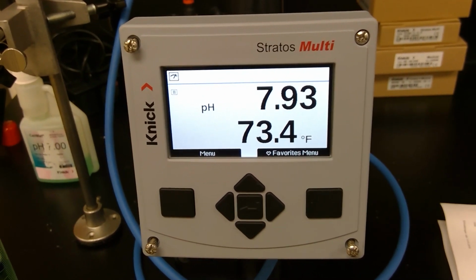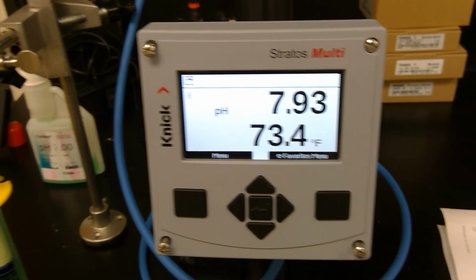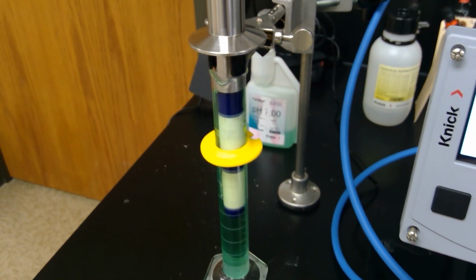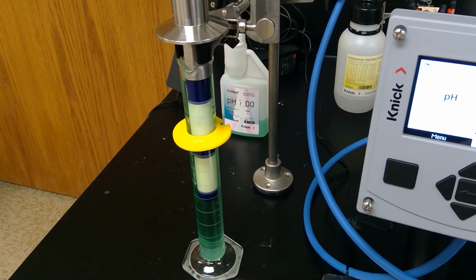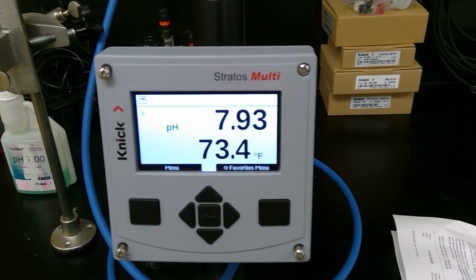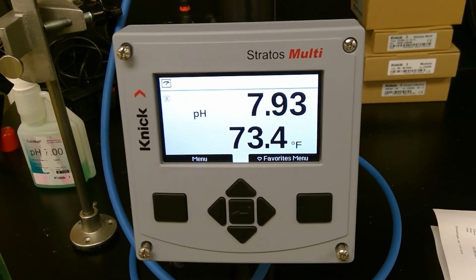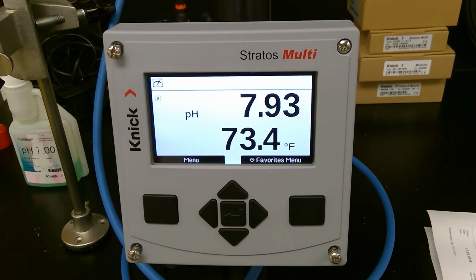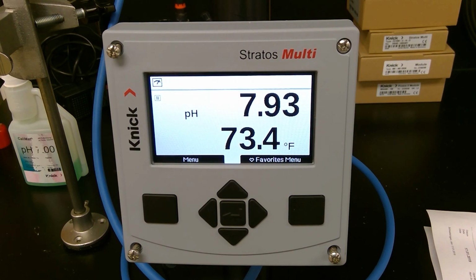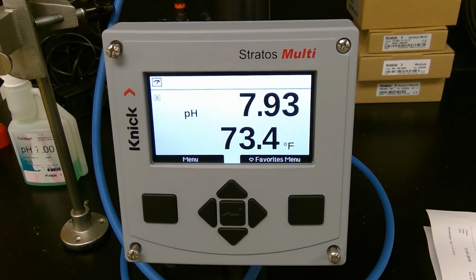So right now, it's reading 7.93. Again, we just configured this, and I currently have it in a buffer 7. So something I want to mention here is that this has been soaking in a buffer 7 overnight. So what we recommend is that if you're taking a brand new Type 18 out of the box, because of the design of that technology where you have a sodium ion selective band on the bottom, hydrogen ion selective band on the top, those two white bands, you want to hydrate the probe before you actually put it in process.